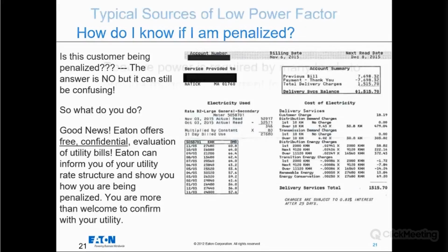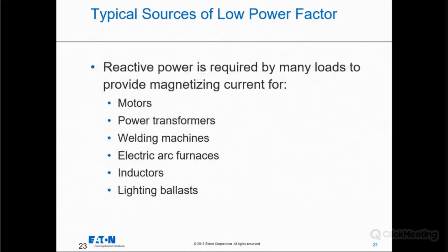So if I'm being penalized, what are some of the offenders that are making me have poor power factor? Well, certainly one of the biggest offenders you'll find in any facility is going to be inductive motors. But there are also other sources. Anything that is an inductive load is going to contribute to poor power factor. So power transformers, welding machines, arc furnaces, inductors themselves, lighting ballast, etc., can cause you poor power factor.